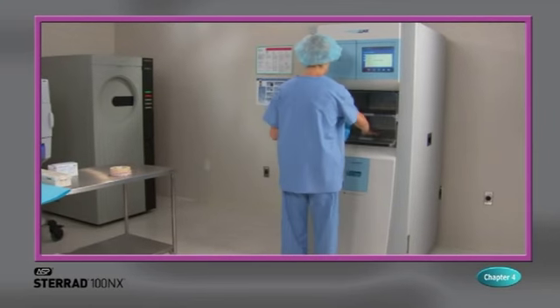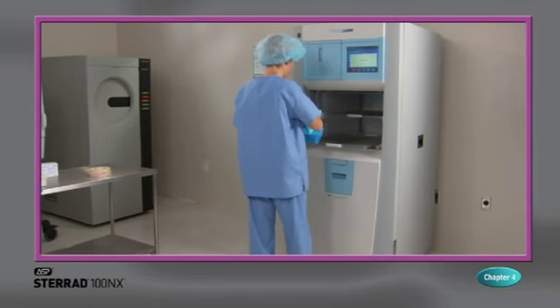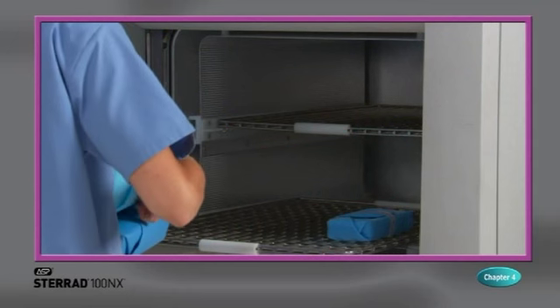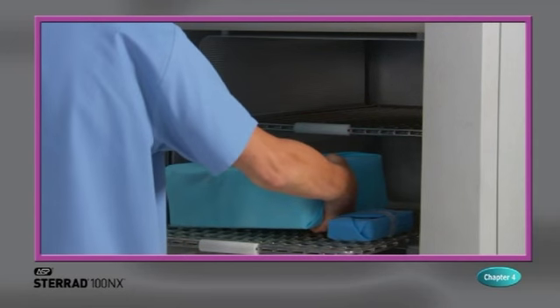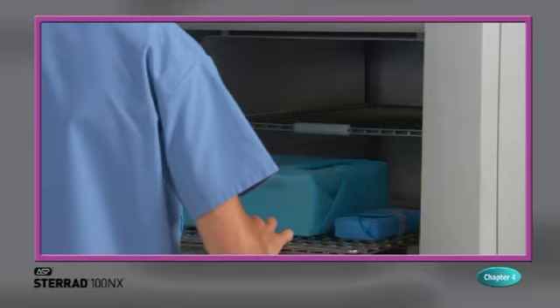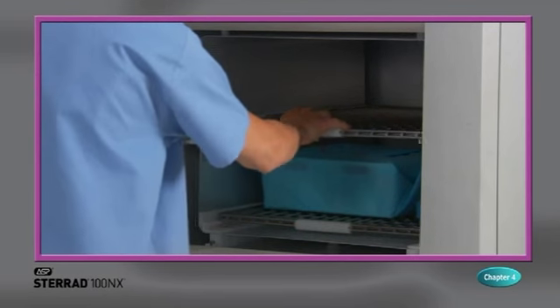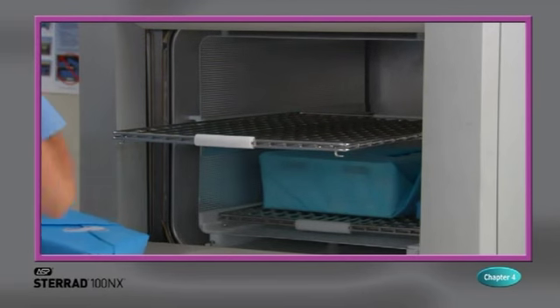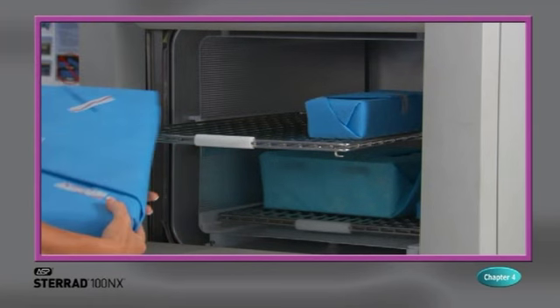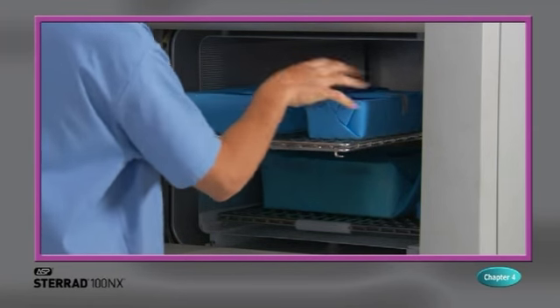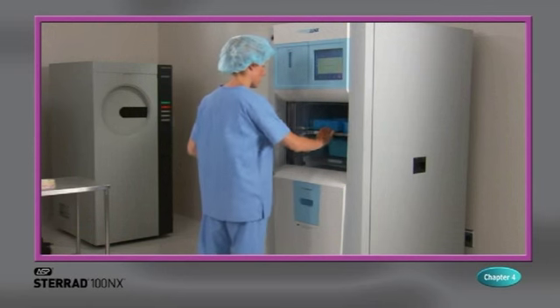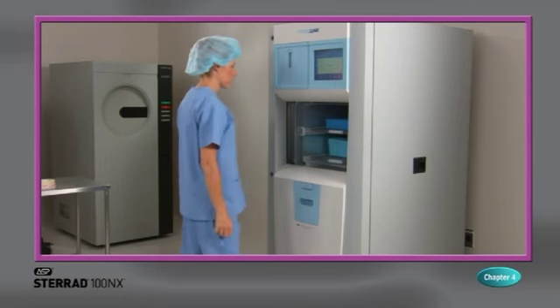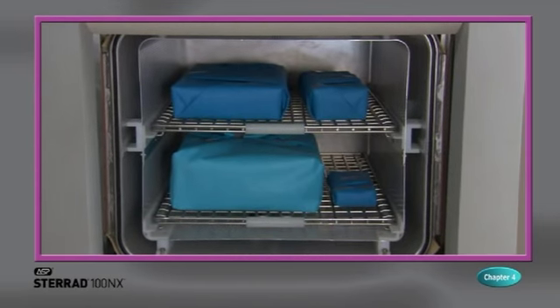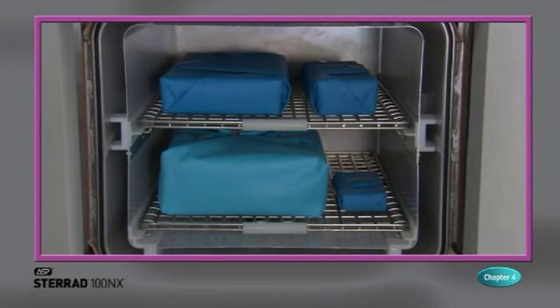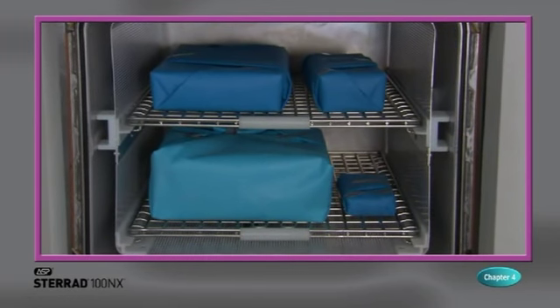When placing the load on the shelves, make certain that you do not block the ultraviolet lamp beam in the front right side of the chamber. Make sure the load is centered on the shelves and that the shelves are centered in the chamber. Do not allow any part of the load to touch the electrode, the back wall of the chamber, or the inside of the door. Leave at least 1 inch or 25 millimeters of free space between the load and the electrode to allow hydrogen peroxide to diffuse around the load.